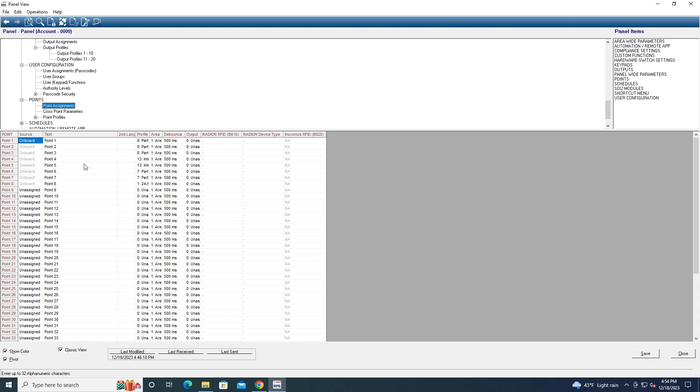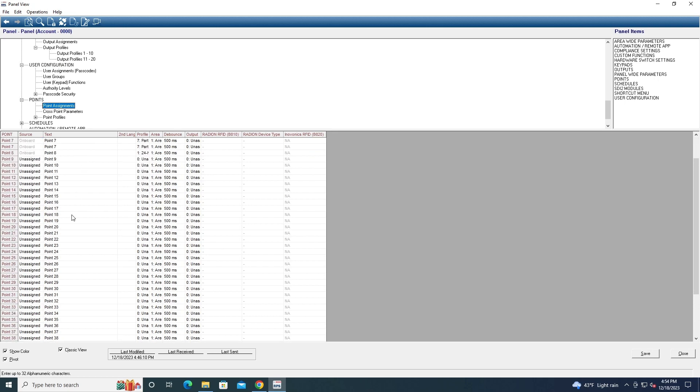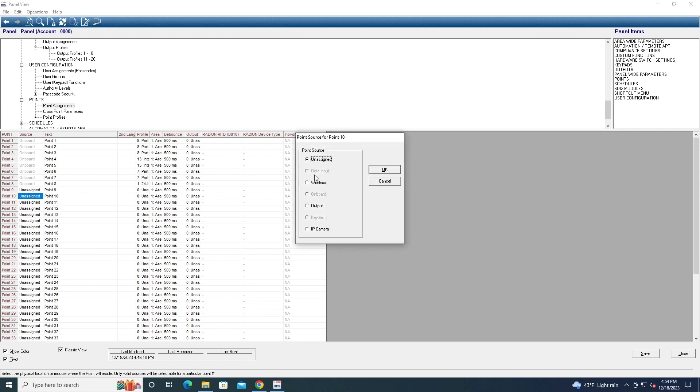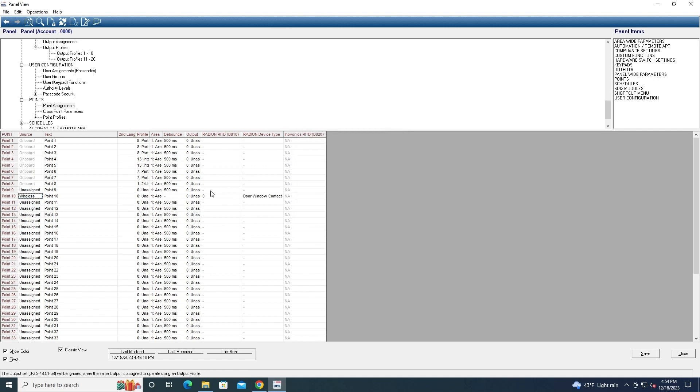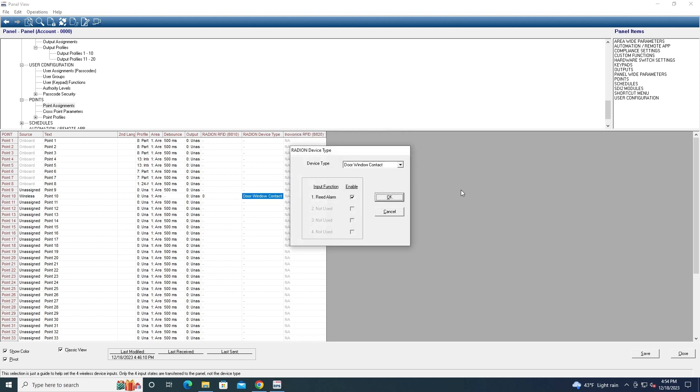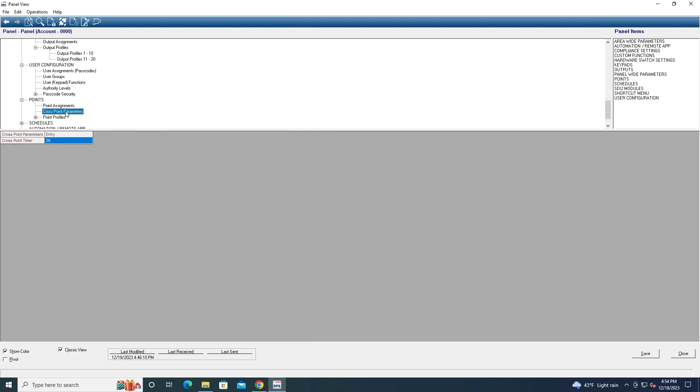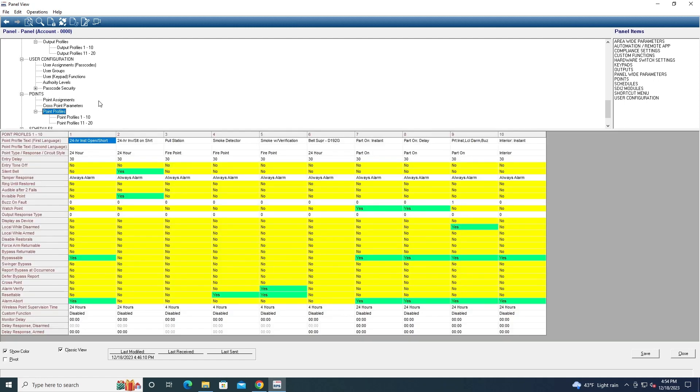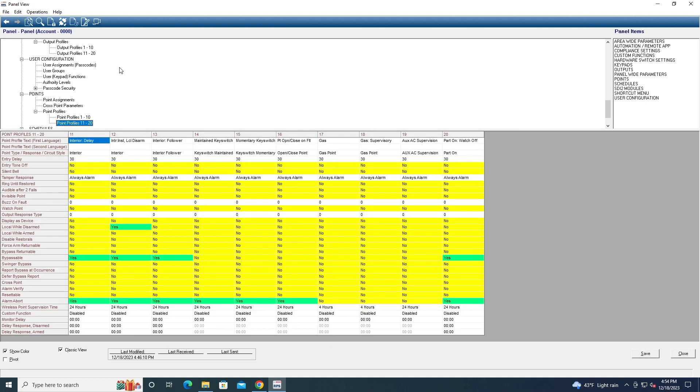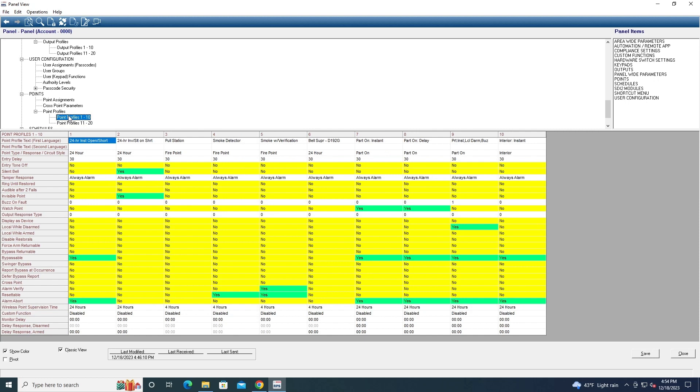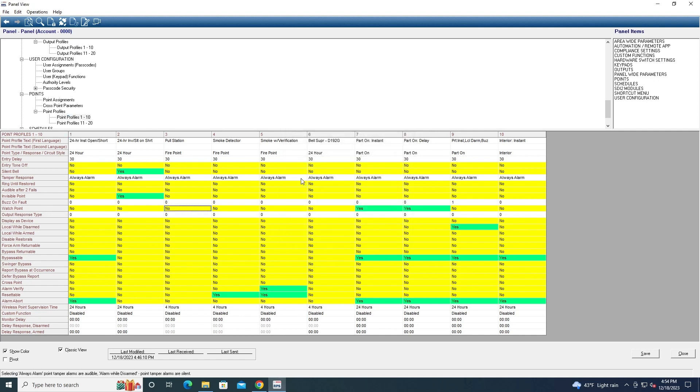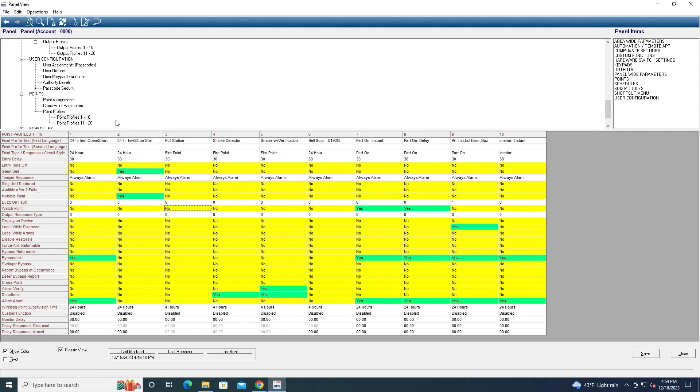And here's where you can configure points. So again, we have up to 48 points on the B5512. For example, if I wanted a wireless point here, you can choose wireless. And let's say it's a door window contact. If it's a wireless device, you will have to have your RADION RFID, which is basically the ID assigned to every wireless point, like on the physical device. Here's our point profiles, which basically you can choose, customize what points do. So for example, if I want a perimeter to have watch point, which that doesn't make sense, but it could do it. But you can choose what kind of points have watch. If it's not common, but sometimes you'll see motion sensors with watch tamper on it. And so if you want that, you can do that.